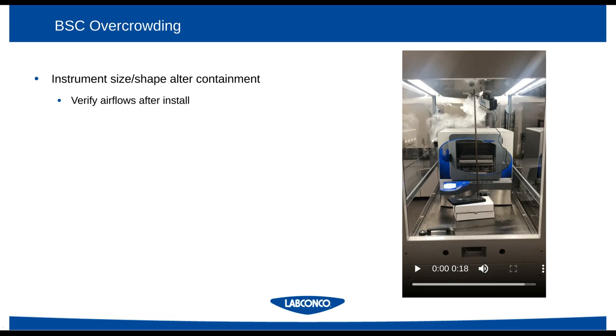This is actually a large freeze dryer. And while generally the performance of the enclosure was compatible with this equipment, you can see the air has to cascade around that device, and in turn does pose an event that creates some disruption and turbulence where the airflow slots are. So it's really important to take note of large equipment inside of enclosures for these types of challenges.